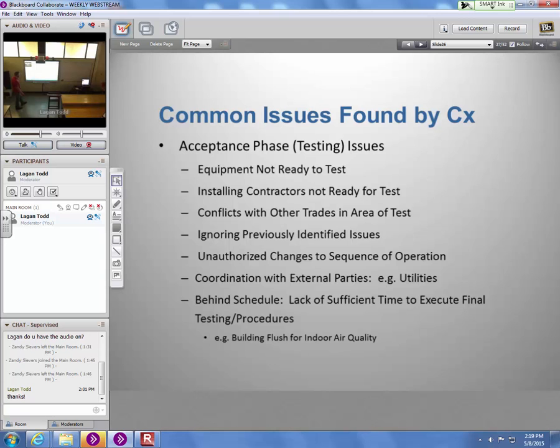Getting behind schedule, there was lack of sufficient time to execute final testing procedures. So the heating hot water system is finished a week before the owner is supposed to move in, and the owner doesn't want us in there testing when they're moving in, so what do we do? We have to watch out for that.